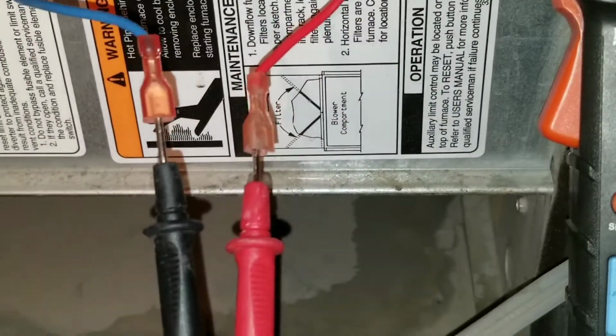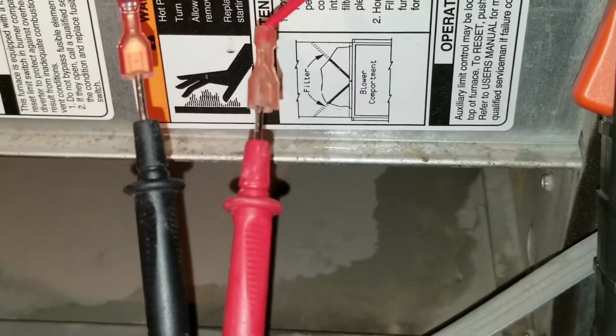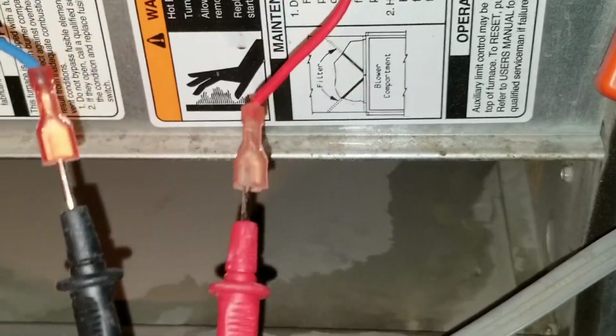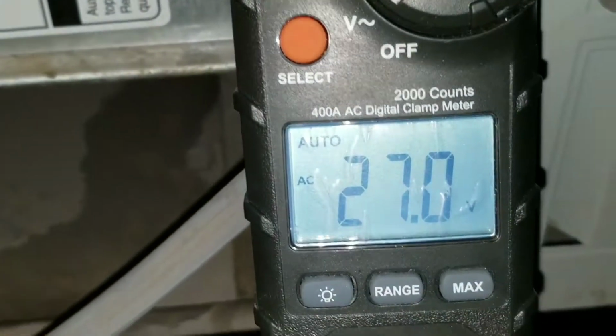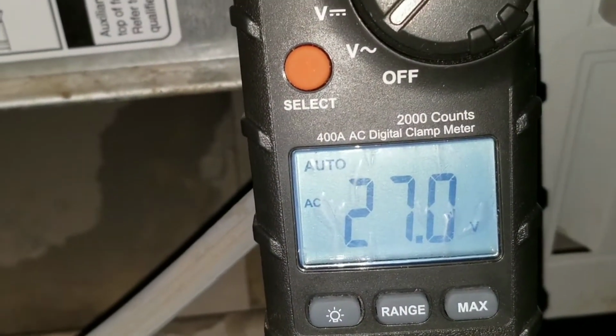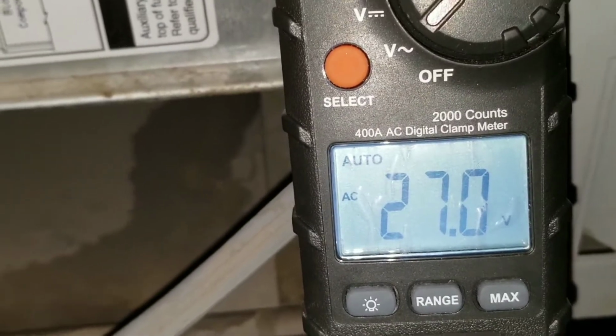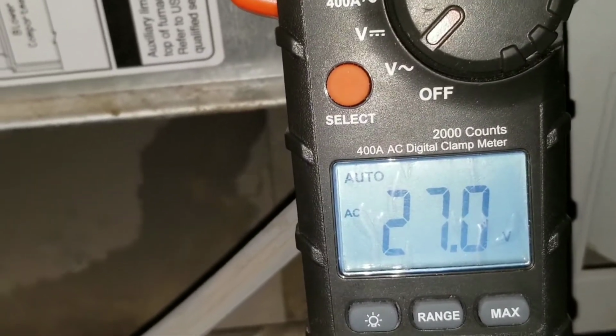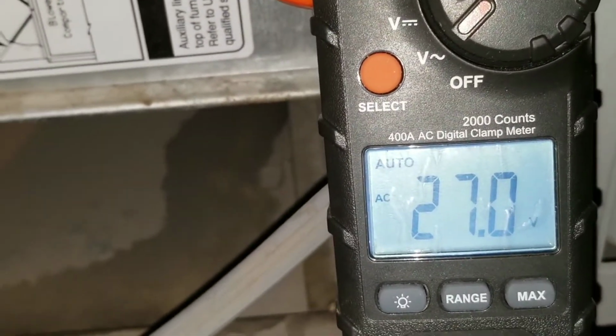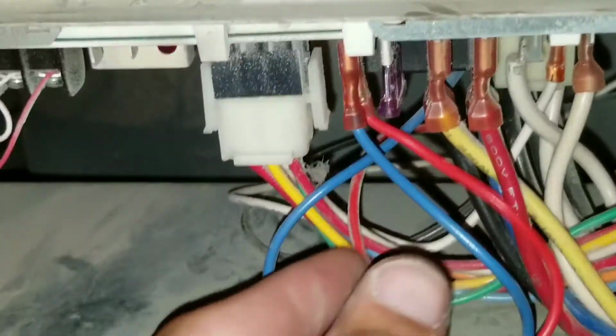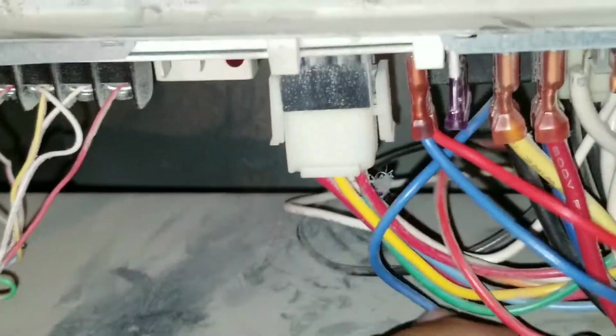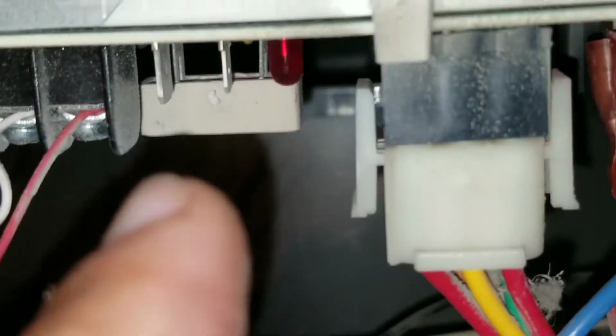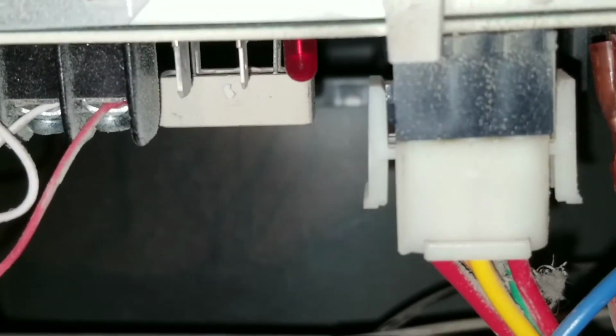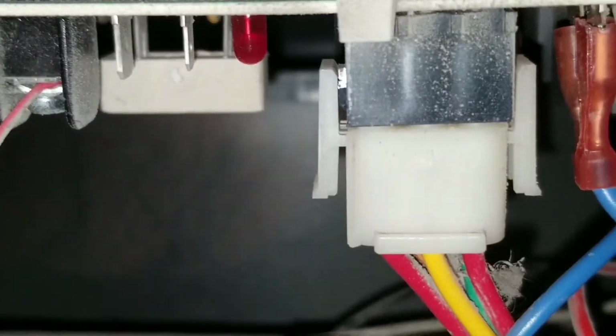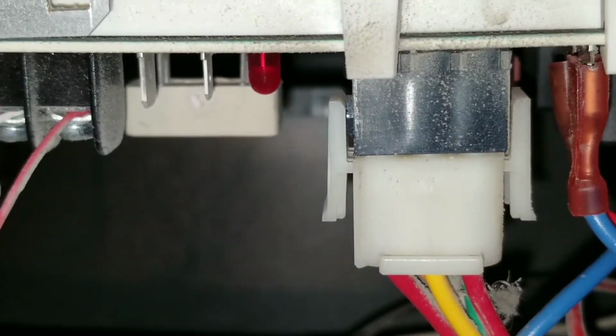So here I just put my multimeter, my probes going inside both leads. So here you can see that I do have 24 volts coming from my transformer. So right now at least we've eliminated the issue of the problem coming from the transformer itself. At this point we're just going to reconnect our two leads. Once I did that, you can see that the LED light is flashing. So that's telling me that my board is getting 24 volts.